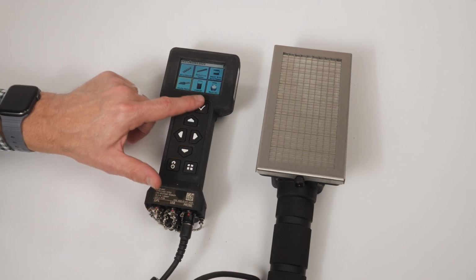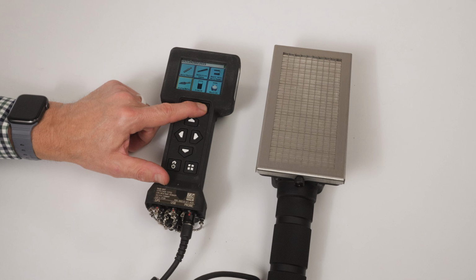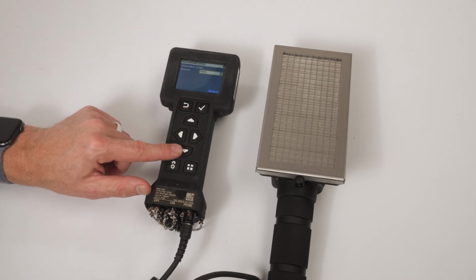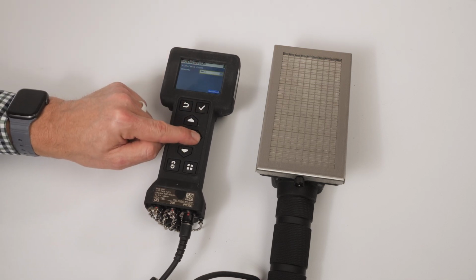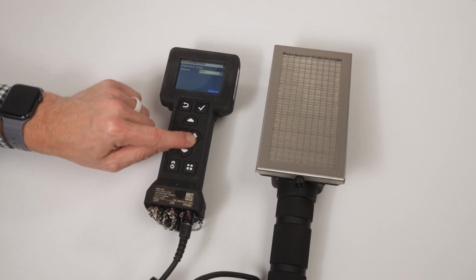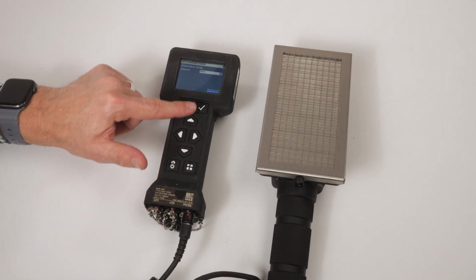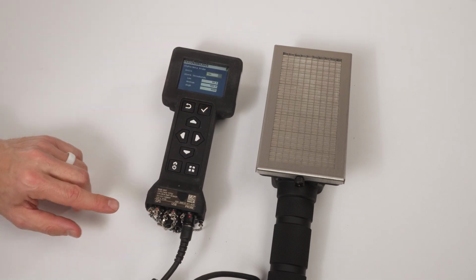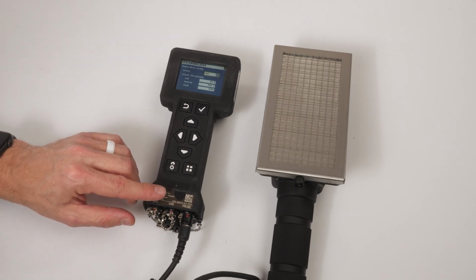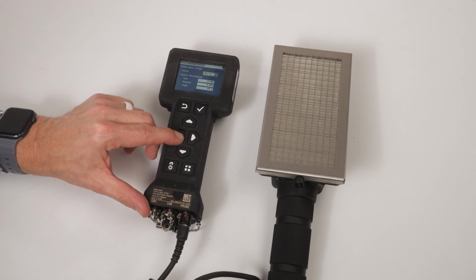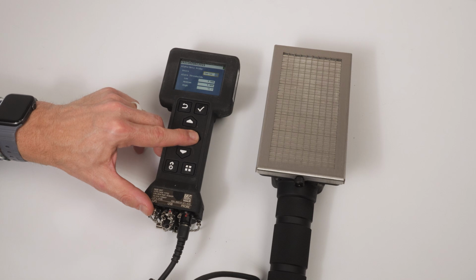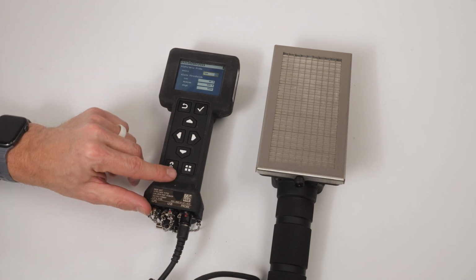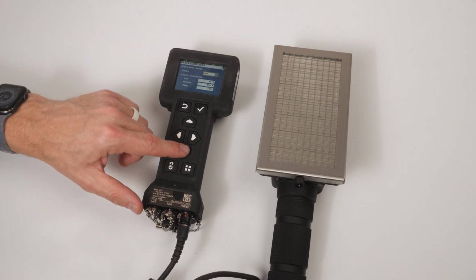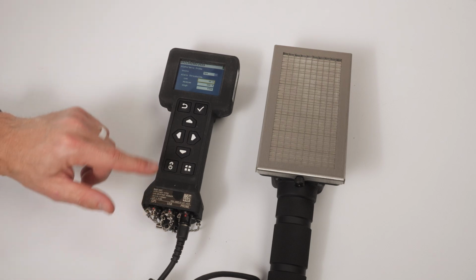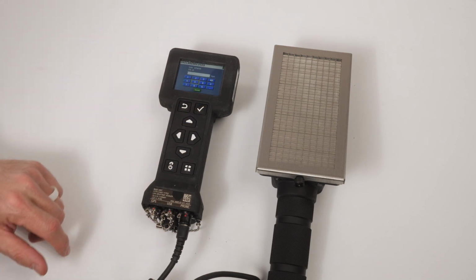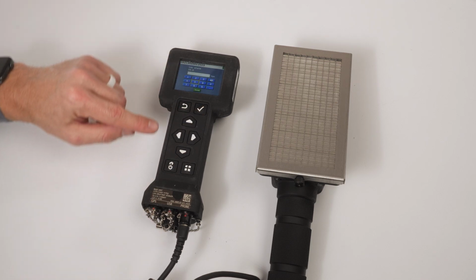Use the arrow keys to highlight the alpha-beta icon and press the enter key to select. Use the arrow keys to change between the alpha channel and the beta channel. Use the arrow keys to highlight the advanced icon and press the enter key. From the probe menu, you can control the units of measure and alarm thresholds. To change alarm thresholds, press the down arrow key to highlight the alarm threshold value you want to change. Then press enter to select that value.